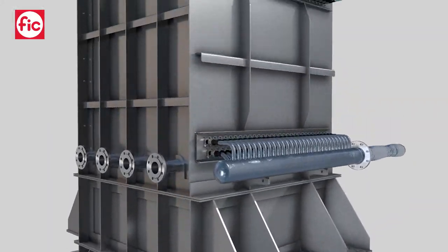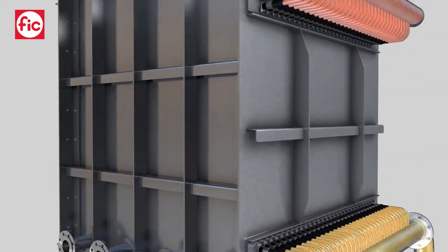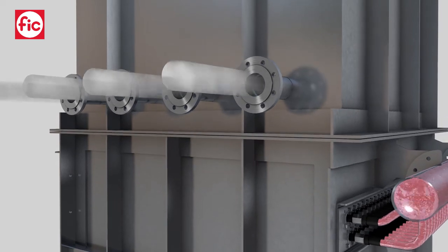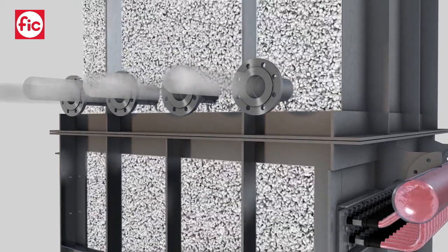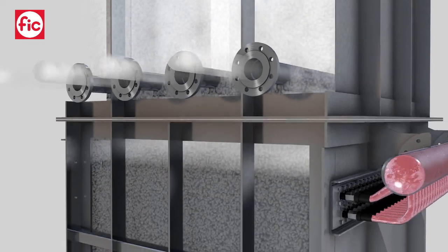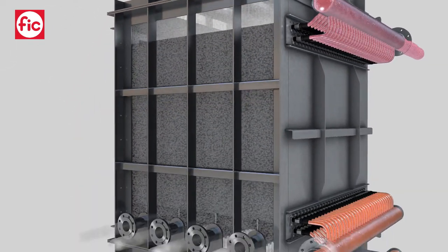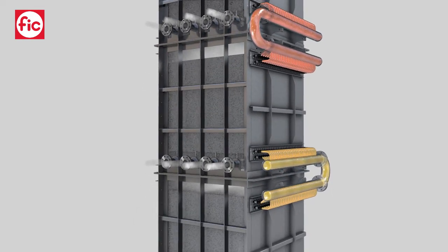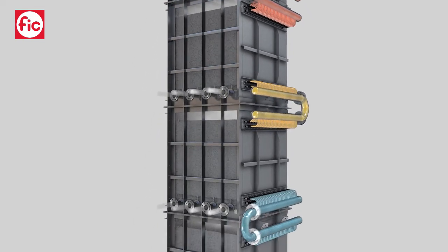The control of humidity to prevent condensation is essential to avoid caking on the thermal plates. A purge air management system blows an accurate amount of purge air in the tower. This is calculated based on a critical relative humidity of the specific product to be treated and on the temperature profiles.